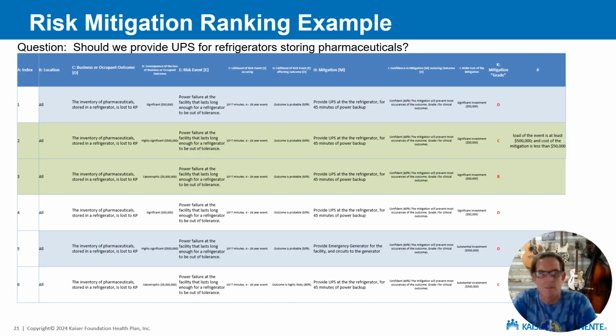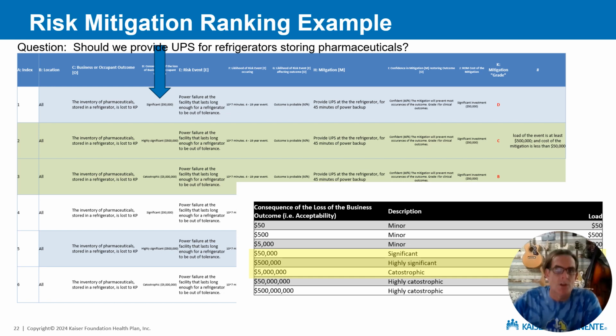So let's look at an example. This is an actual example. This question came up several years ago. Should we provide UPSs for refrigerators that are storing pharmaceuticals? So the first thing is the load or the consequence. And so would the loss be in the range of $50, $500, $5,000, $50,000, $500,000, or $5 million? So in this example, there's actually 6 lines. The top 3 lines look at 3 different loads, and then the bottom 3 lines repeat that. But in the top 3 lines, we're looking at $50,000 losses, $500,000 losses, and $5 million losses, right? That's the load that we're going to look at, and we're repeating that twice in this case.